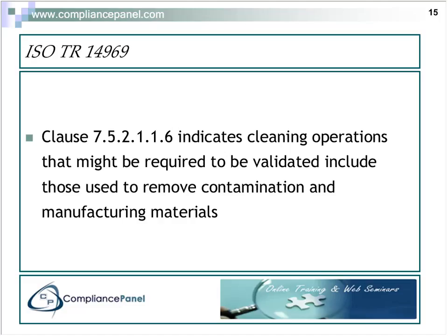And it does say that cleaning operations that might be required to be validated include those used to remove contamination and manufacturing materials. So if you have a manufacturing process that requires the use of some kind of manufacturing material to expedite it, some examples might be things like mold releases.